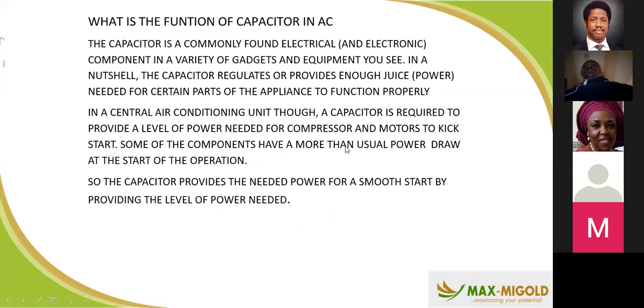The compressor has a high starting current, so when you plug it in, because the capacitor is close to it, it aids the compressor to attain the power it requires to start. If you remove a capacitor, at no time should you use your bare hand to touch it, because it has electrical charges in it. It can kill if they are bigger, and it can electrocute. Electrocution might not totally kill you, but it can damage your tissue, so you need to be careful handling a capacitor.